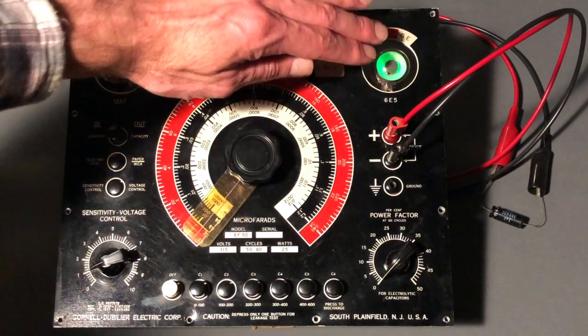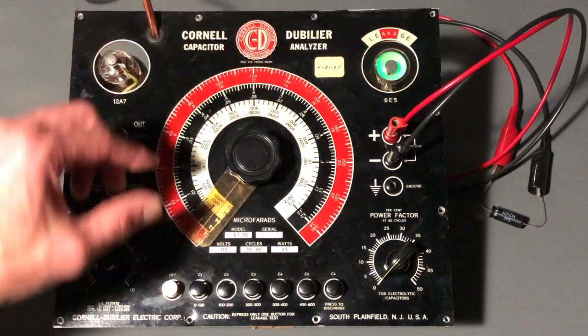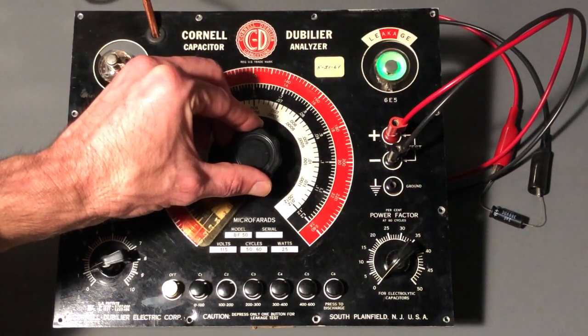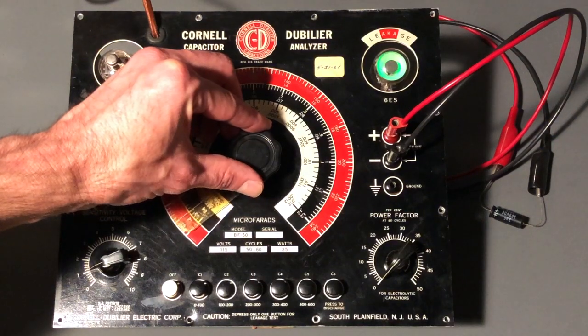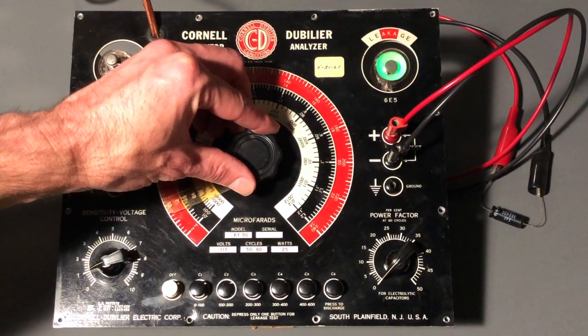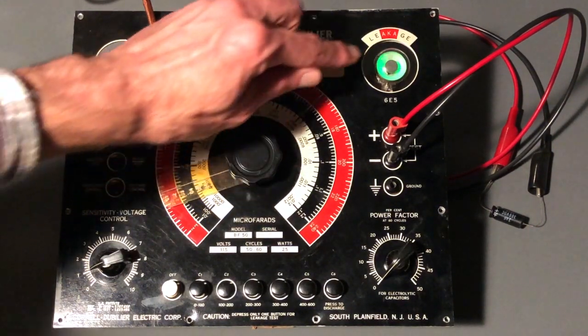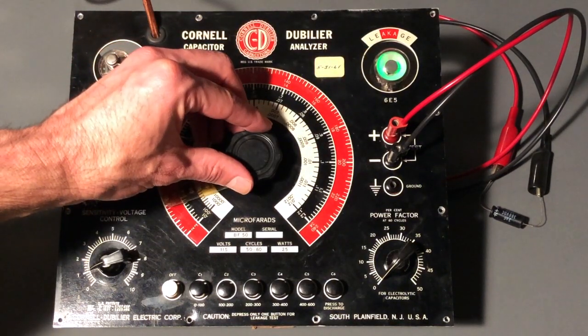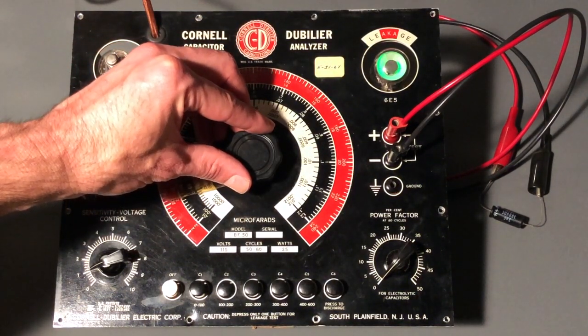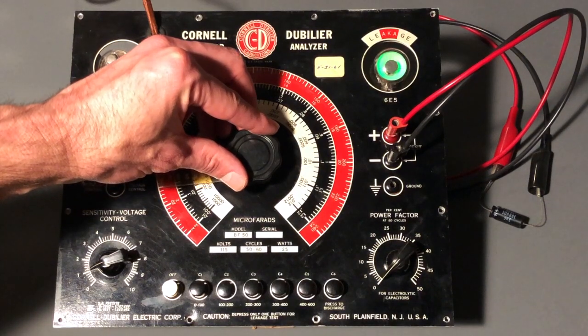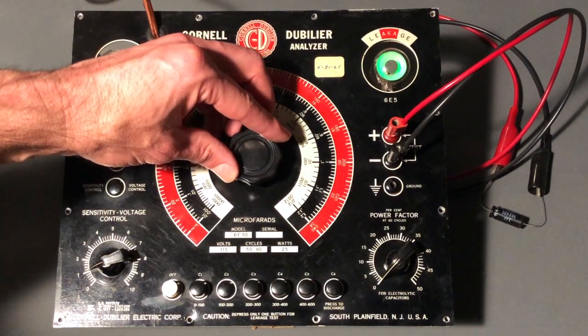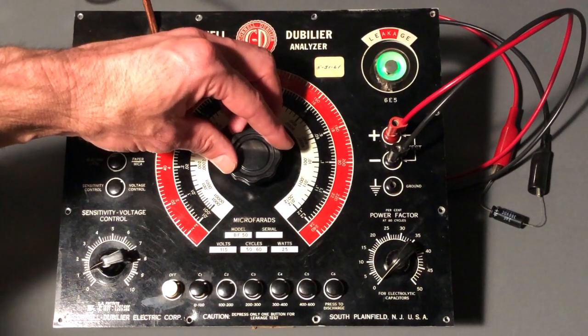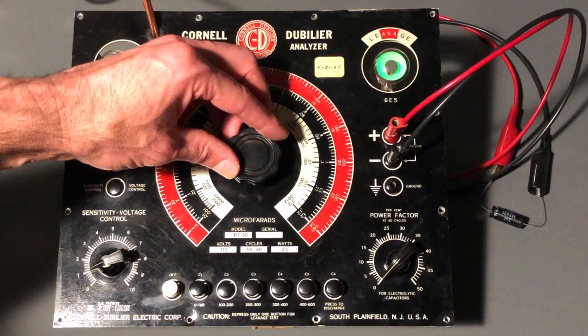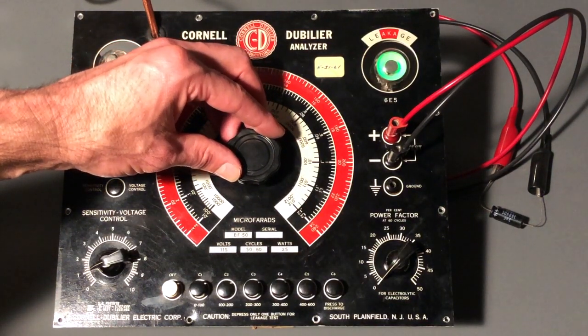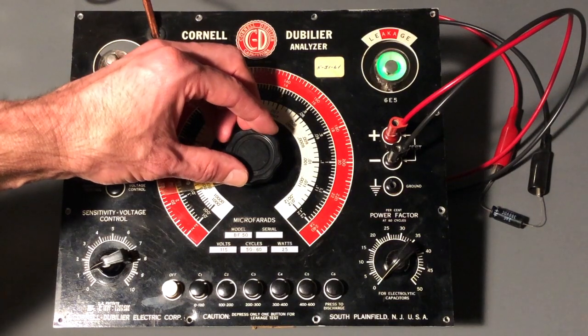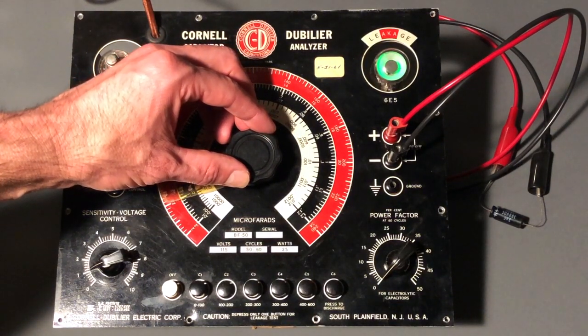So watching the eye tube over here, you can see it's closed right now, it's a solid green. I'll begin to slowly increase this up. And you can see the eye is now starting to open. So that's a good sign. And now the eye is closing again, so any further movement, the eye remains closed. So we want to back up, turn the dial back down to the point when that eye reaches a maximum opening.